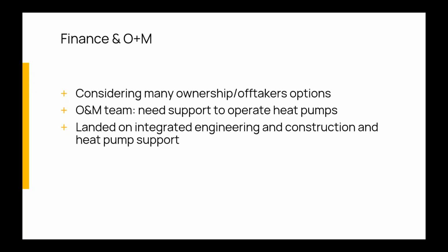When we look at operating and maintenance, if we end up having our own loop, this would be unique—we don't operate a 5th gen type system anywhere else. Our new life sciences building is going to be quite complicated, and then we're adding new stuff for decarbonization. Do we want the O&M expertise in-house, or do we want to sub some or all of it out? A lot of our chiller maintenance is contracted out—we respond when there's a problem, but we don't replace motherboards in them. So there's going to be the right balance for operation and maintenance, and basically ecosystem guided us through a process where we landed on an integrated system, doing a little of both.